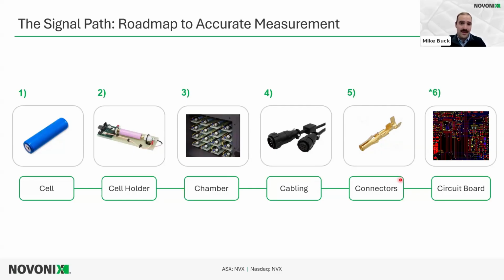Another overlooked area in the build and design process is the connections themselves and the material of the connectors. If you have dissimilar metals in the junctions, this usually creates what's called a Seebeck effect—similar to how a thermocouple measures temperature. Different materials, the dissimilar metals, create voltage discrepancies. All those voltage discrepancies throughout the junction points—if it's copper to gold to silver to different metals—will end up having different voltage drops, and that will skew your readings. So maintaining the best conductive materials and keeping connectors as consistent as possible through the signal chain is critical to keeping a high precision measurement system operating as expected.